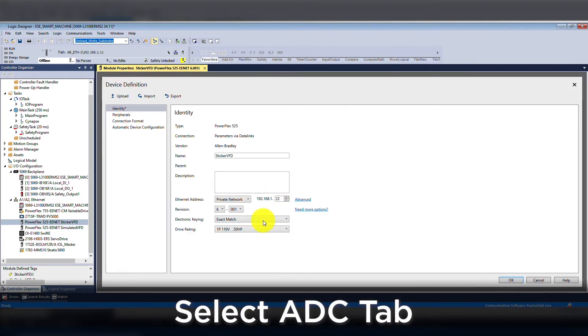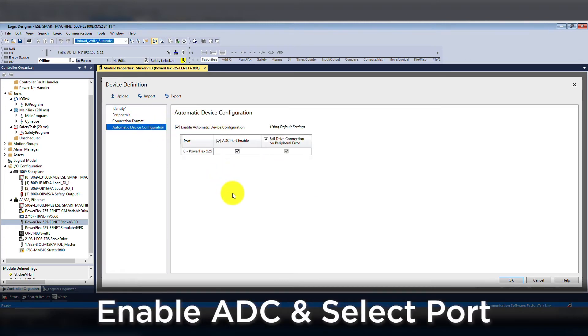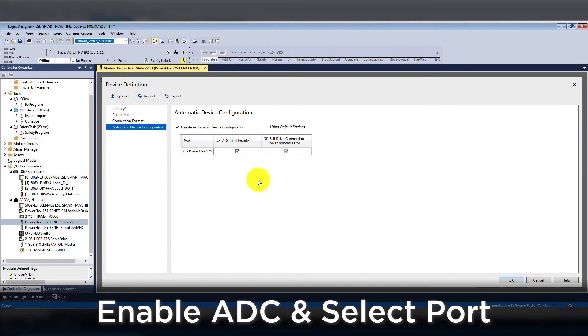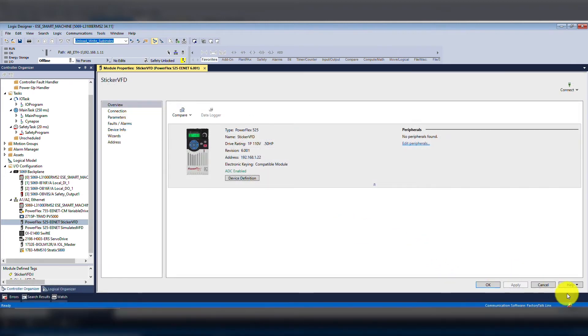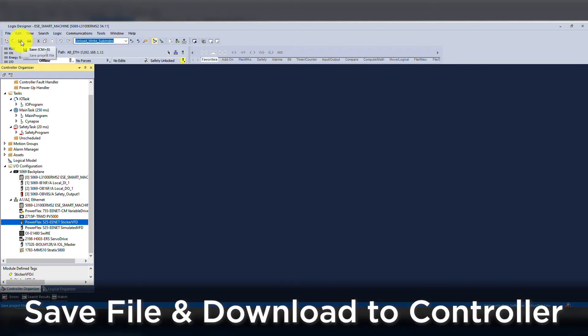In the module definition, you will see the tab called automatic device configuration. Once you select the tab, you will see the checkbox to enable ADC and select the proper port. It's important to select the proper port if you have multiple communication paths to the drive. Once the module definition is set up and we've uploaded the parameter set, you will need to save the file and download it to the controller.